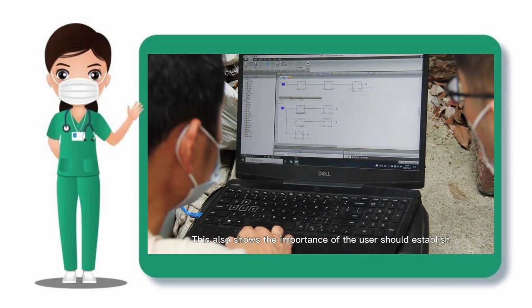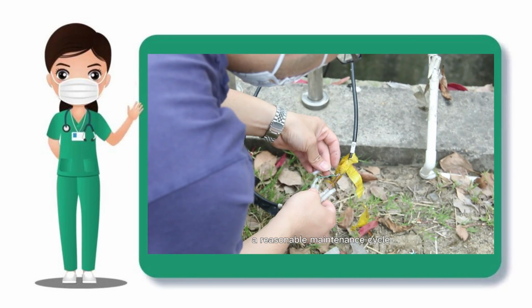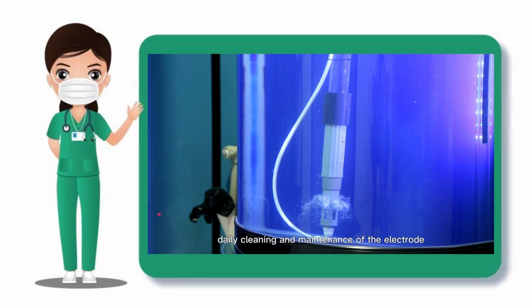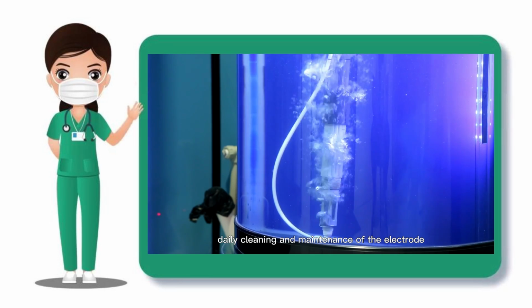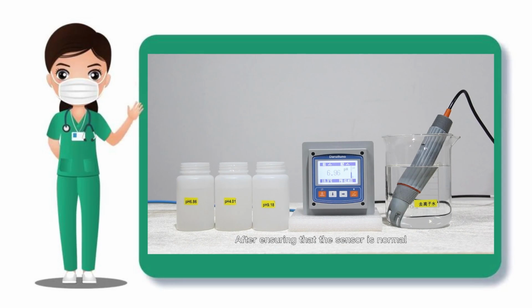This also shows the importance of the user establishing a reasonable maintenance cycle. Daily cleaning and maintenance of the electrode. Daily calibration. After ensuring that the sensor is normal, you can enter the second stage, sensor calibration.